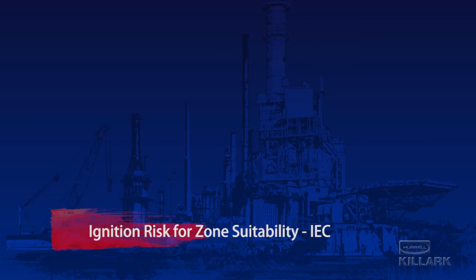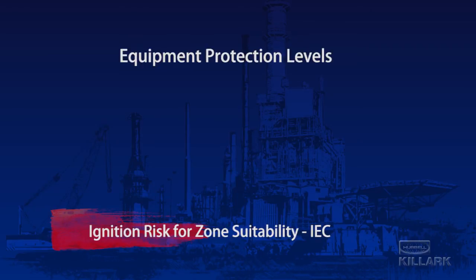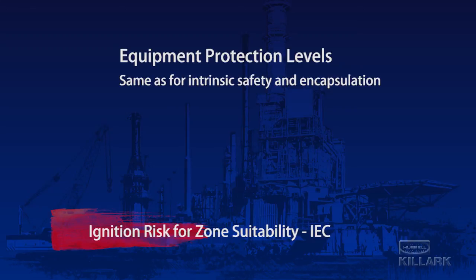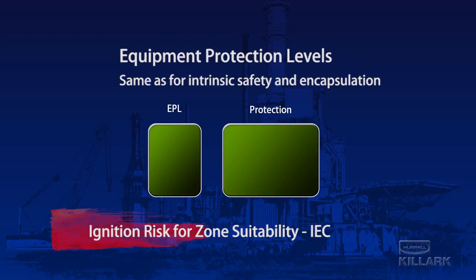The IEC uses nearly the same definitions for determining its Equipment Protection Level, or EPL. However, in the case of the IEC, the same letter designations are used for the different levels of protection that are also used for intrinsic safety and encapsulation. Equipment Protection Level A is a very high protection level. EPL-B is a high level of protection, and EPL-C is a standard or normal level. Again, the addition of the letter G indicates a gas or vapor hazard.